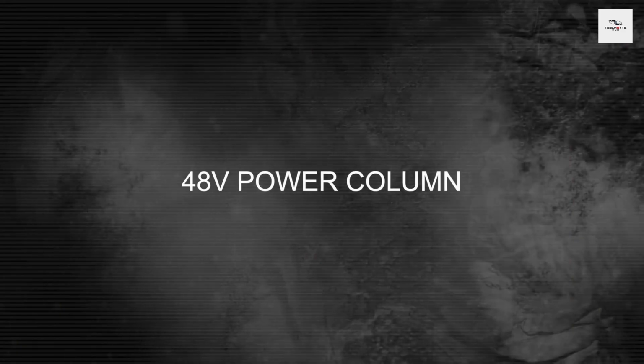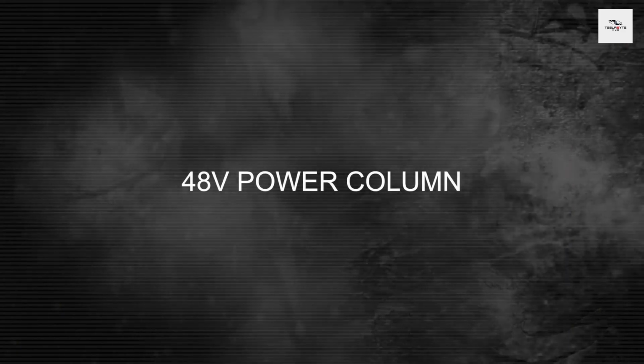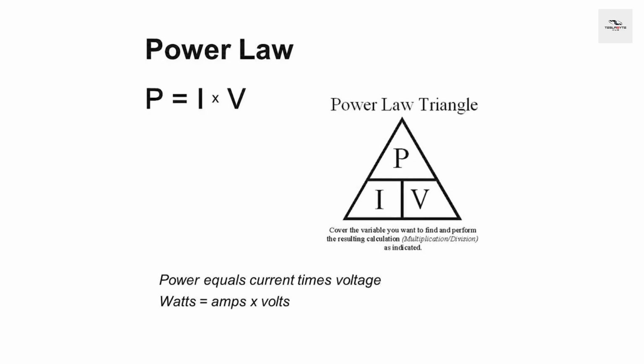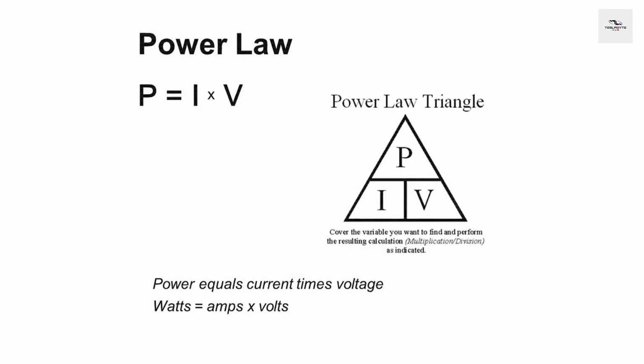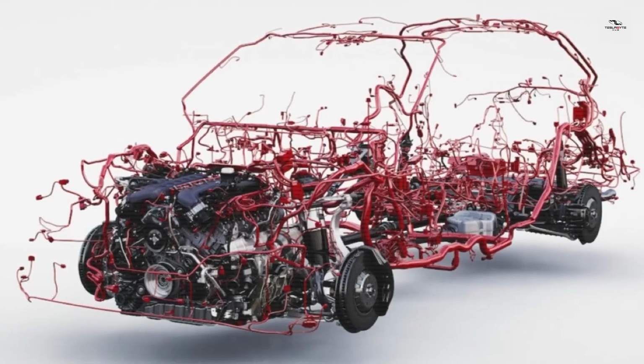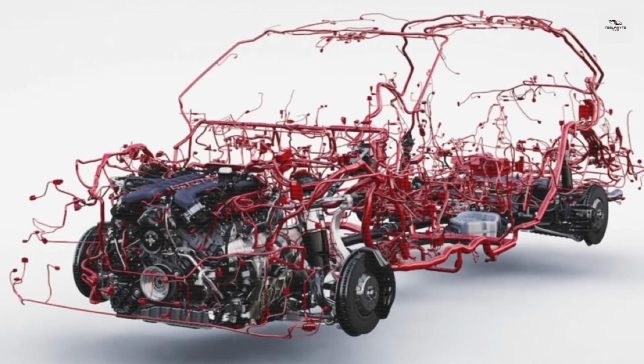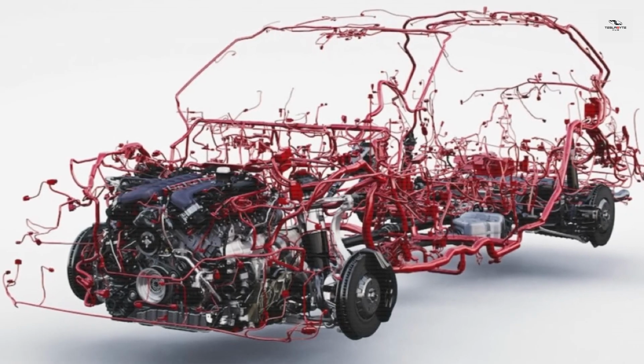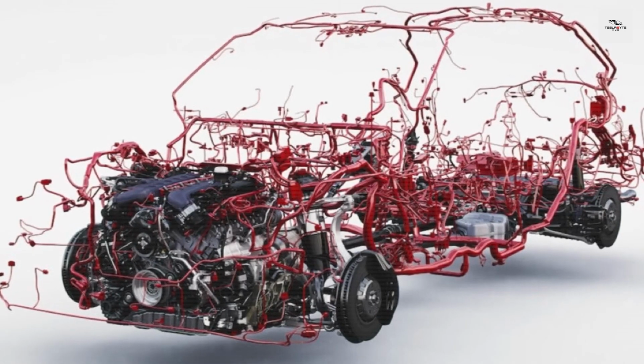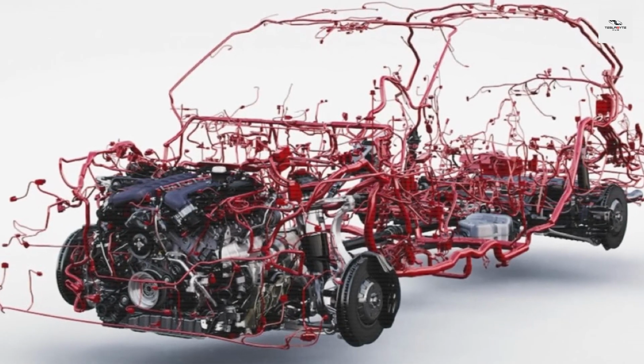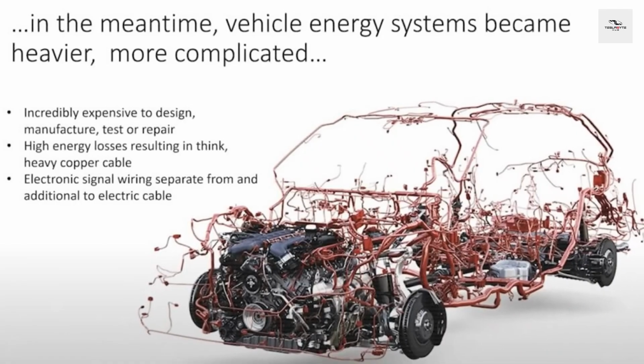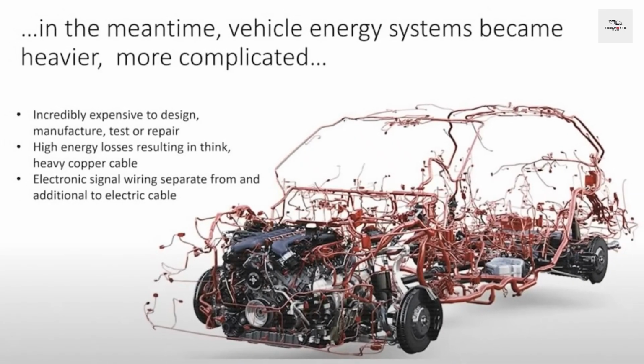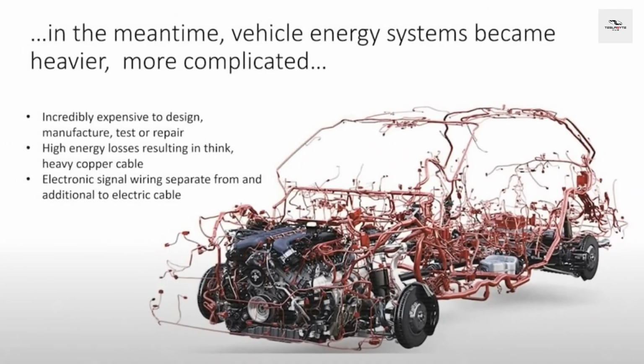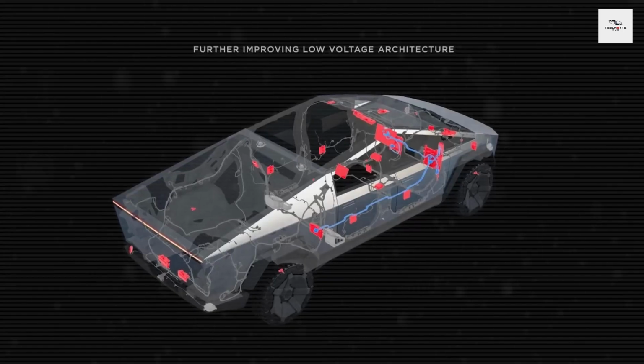A 48-volt power supply with standardized quick-swap connectors follows a simple principle: power equals voltage times current. A 960-watt load that needs nearly 80 amps at 12 volts needs only about 20 amps at 48 volts. Because wire loss grows with the square of current, cutting current slashes heat and wasted energy.